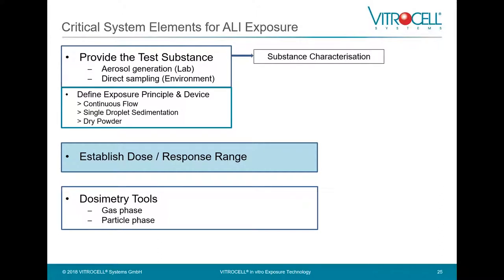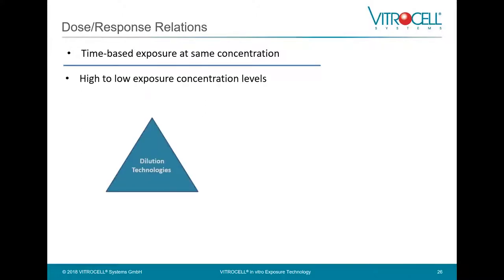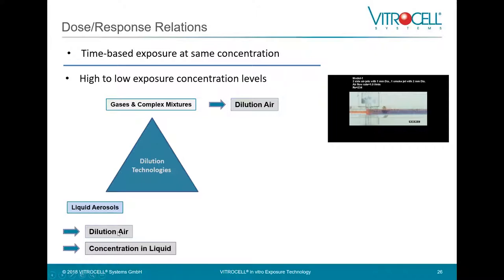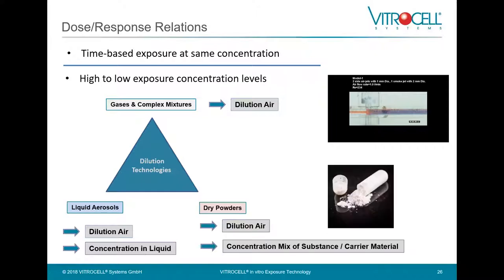To establish a dose-response range, you can start with a time-based exposure at the same concentration — exposing for 20 minutes up to 4 hours — and compare the time-based effect. Alternatively, you can work with high-to-low exposure concentration levels. For gases and complex mixtures, this is done by adding dilution air dynamically, varying the substance concentration. Liquid aerosols can also be diluted with air or by working with the concentration in the liquid. Dry powders can similarly be diluted with air or by adjusting the concentration mix of the substance with the carrier material.